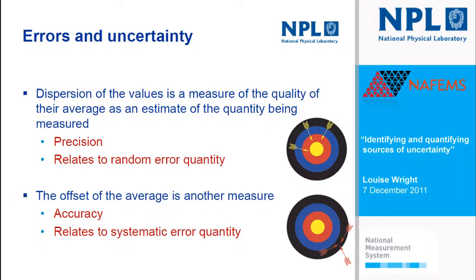We tend to separate uncertainties into two different types. The first is random uncertainties, typified by the scatter shown in the arrows at the top, and that's basically quantified by a standard deviation. The second type is more to do with accuracy issues — values close together but offset from the centre. Normally you'd remove all accuracy issues, but in some cases you're not able to describe them sufficiently well to remove them, so you have to take them into account as an uncertainty rather than an error.